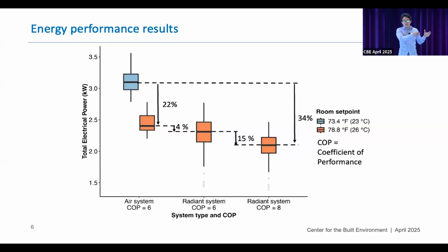We don't have our dedicated chiller for that space, so we are taking chilled water from the central system. It's roughly about a COP of 6. But the thing is, since we are separating both the sensible cooling and the latent cooling here, if the sensible cooling was using a much higher COP chiller, because you don't need that cold of a water for providing sensible cooling, you can immediately drop another 15% of energy consumption here.